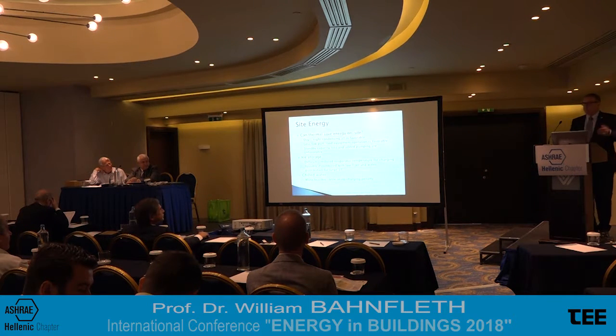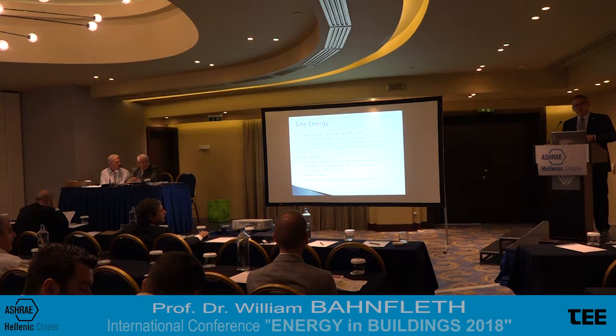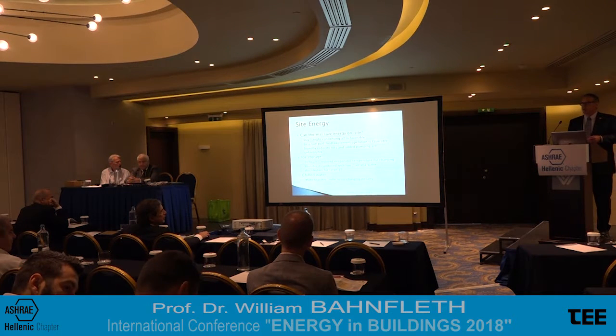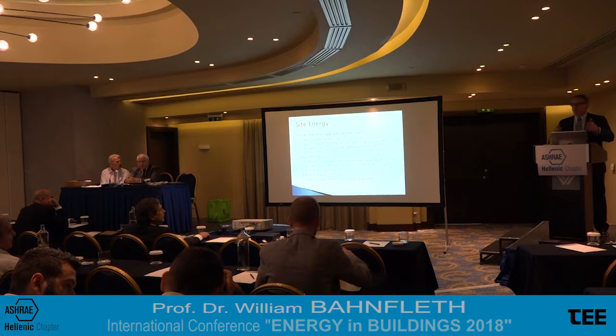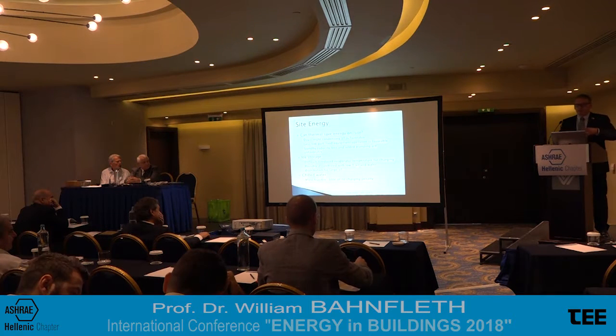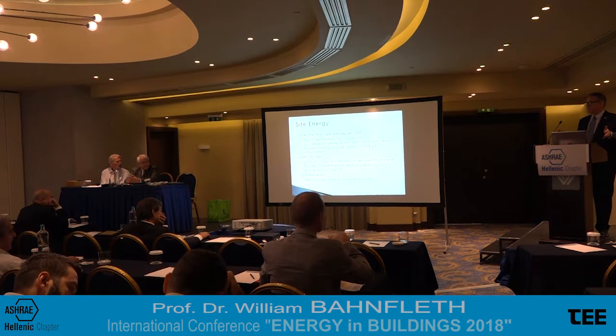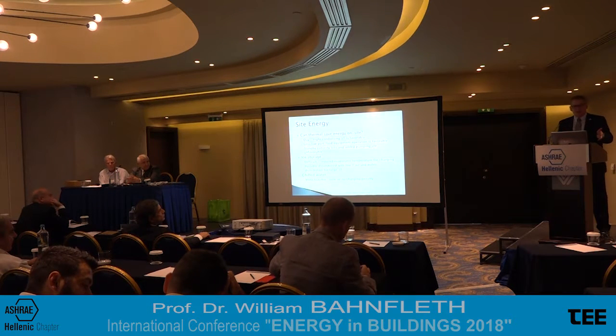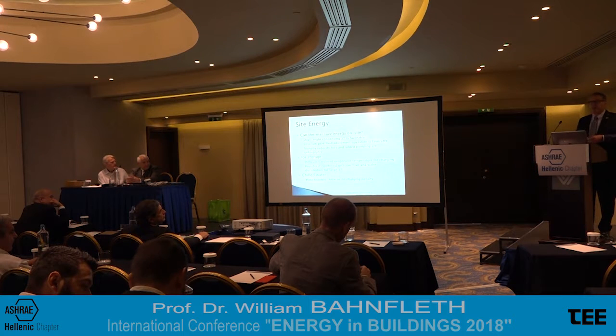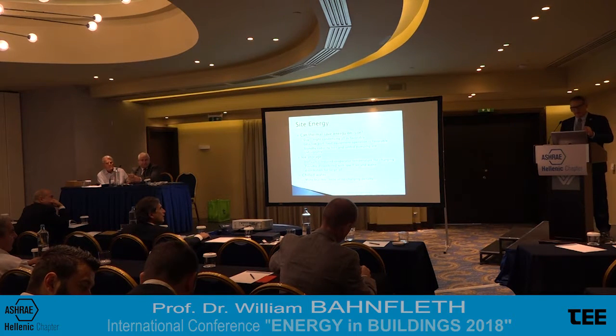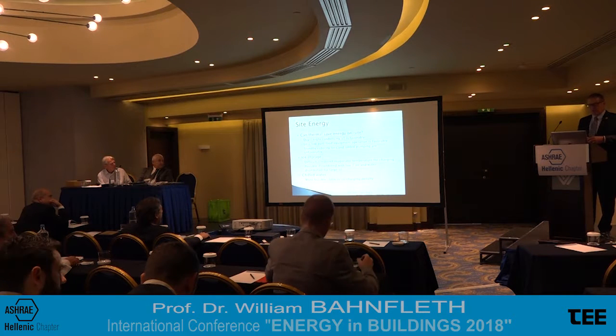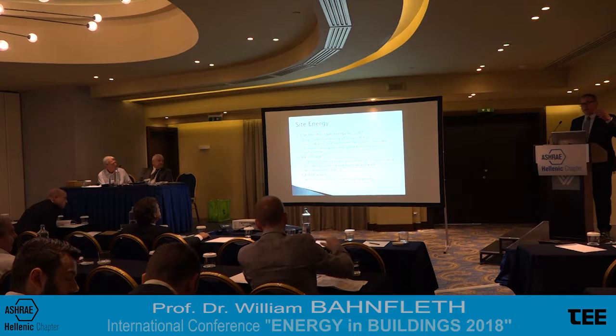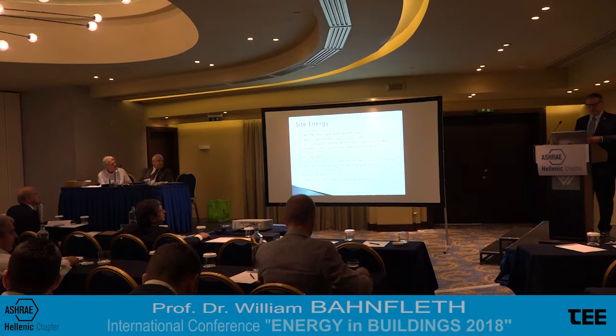Ice storage, I will freely admit that I'm not a big fan of ice storage, because when I was a consultant, I mainly worked on large systems, and I couldn't quite justify dealing with the energy penalty that comes with ice storage from having to use such a low evaporating temperature to make it. So if your goal is to save energy with thermal storage, the best way to start is probably not to dig yourself a big energy hole that you have to get out of in other ways. But actually, you can still have an ice storage system that in some cases will use less energy than a conventional system if it's air-cooled and if you're using the low temperature source advantageously.